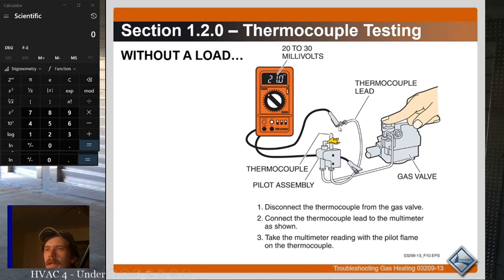Alright, and you read the voltage in millivolts AC, right, millivolts. Might be DC, whatever. It's usually the only millivolts you have on your meter anyway. You need a meter that has a millivolt setting, and you need to check it from the tip to ground. And you should have generally 20 to 30 millivolts, but thermopiles can be more. If you run across a thermopile, sometimes those are 200 to 300 millivolts. But you want to know on a regular thermocouple it's going to be 20 to 30. On something that has a thermopile, you might want to know what the manufacturer calls for as far as millivoltage. But you'll just check that.